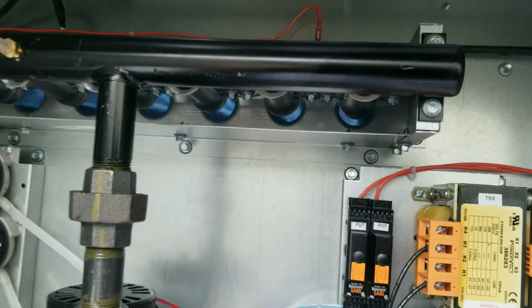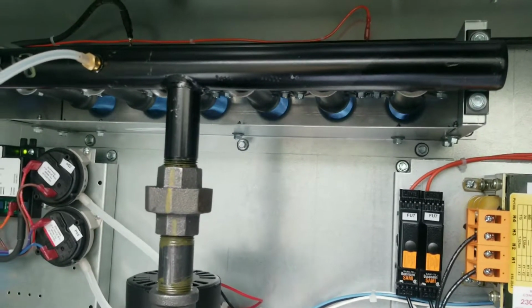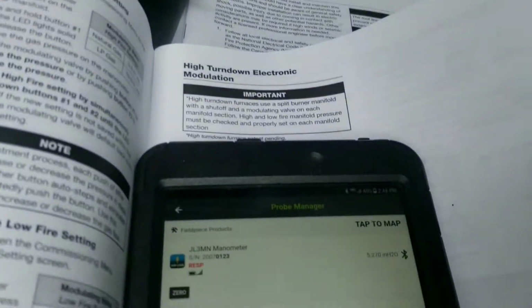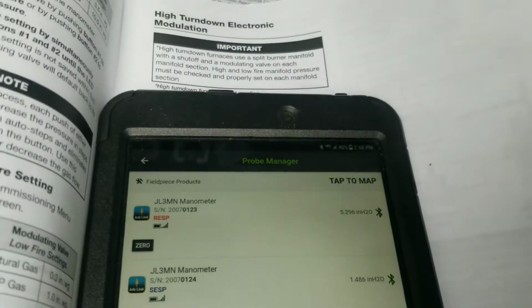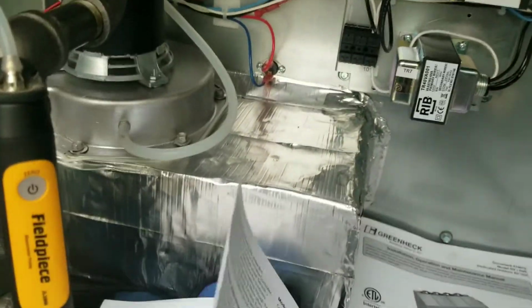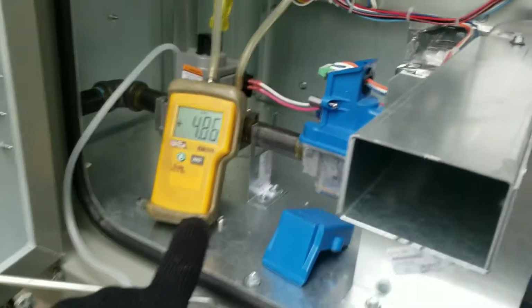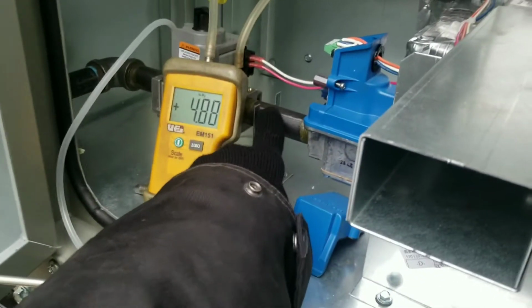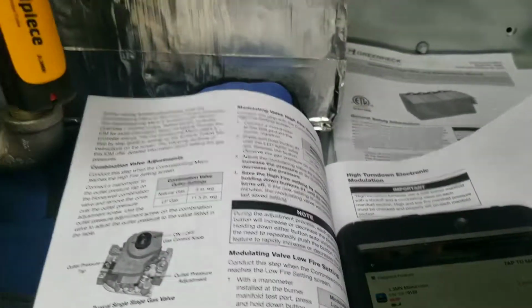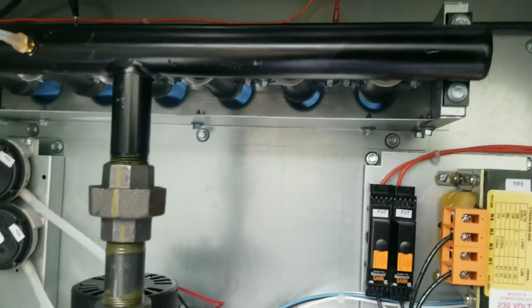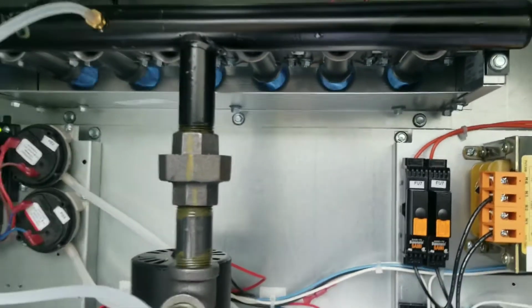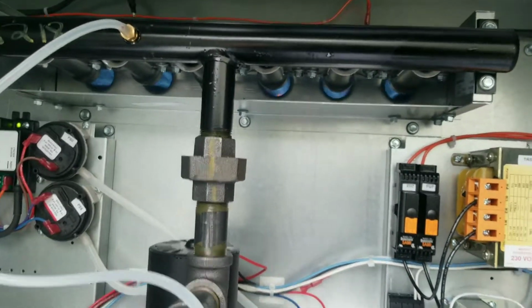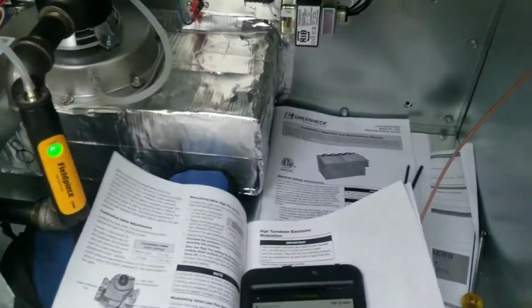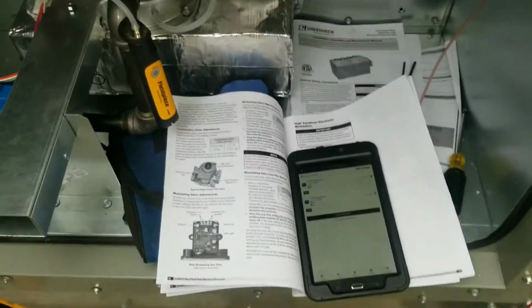That might just be a pressure to the building. This is low pressure, so I don't have a regulator to adjust. I started out at 7.9, 8 inches water column in, and you can see I'm at 5 now. So as that inlet pressure drops, outlet pressure of that gas valve drops. That's my outlet here. Still modulating down. Kind of throws everything off with that inlet gas pressure fluctuating like it is. But I think this guy's gonna work just fine until we can get something solved on the inlet gas pressure.